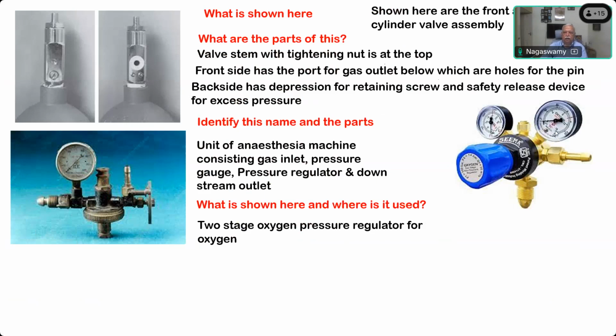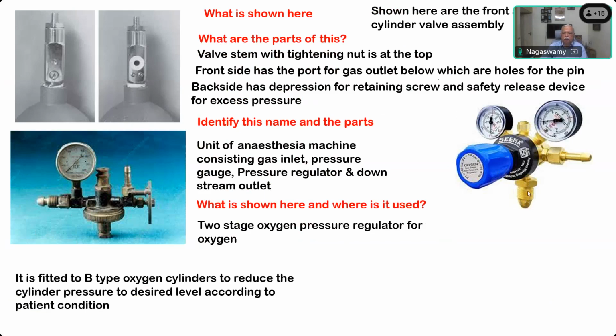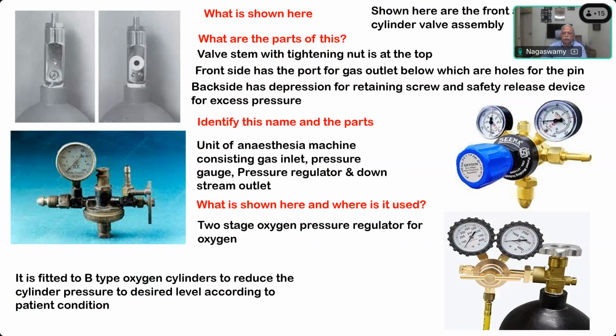So there are two regulators, and you can see two outlets which will go to the patient. And this is the probe, the point where it has to be attached to the cylinder. And that is how, by turning this knob, you can adjust the pressure as you want it. So it is fitted to the B-type oxygen cylinders to reduce the cylinder pressure to the desired level according to the patient condition. This will give you an idea how this is connected. Anybody knows the name of this? This is to open the stem to allow the gas to flow here.